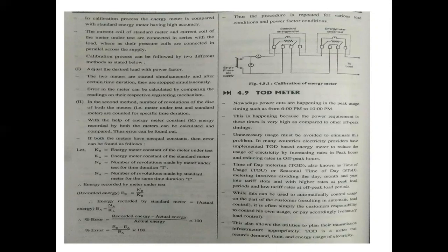The error in the meter can be calculated by comparing the readings on their respective registering mechanisms. If the standard energy meter shows reading X and the meter under test shows reading Y, then the difference between them is the error. In the second method, the number of revolutions of the disk of both meters are counted for a specific time duration. With the help of the energy meter constant, the energy recorded by both meters can be calculated using the formula: Energy recorded = Number of revolutions / Energy meter constant.